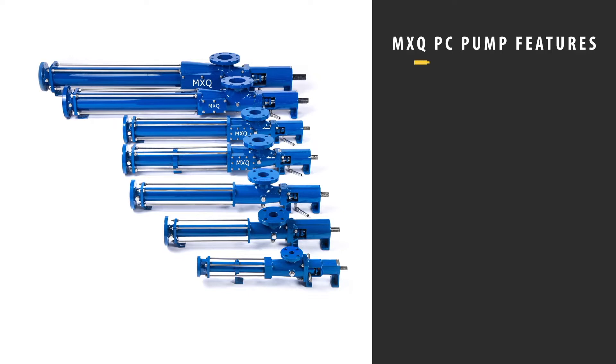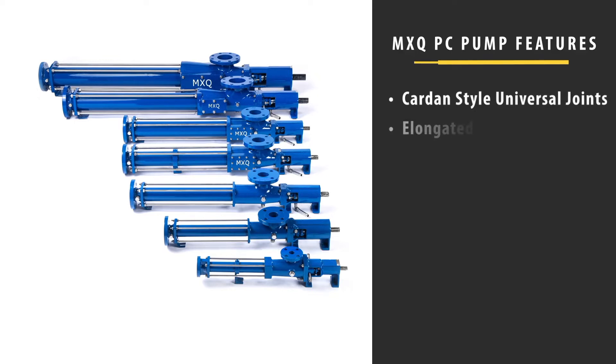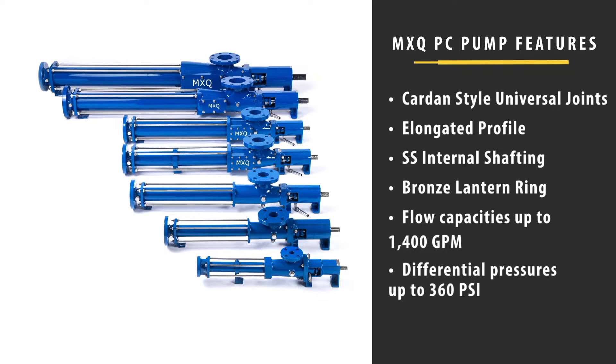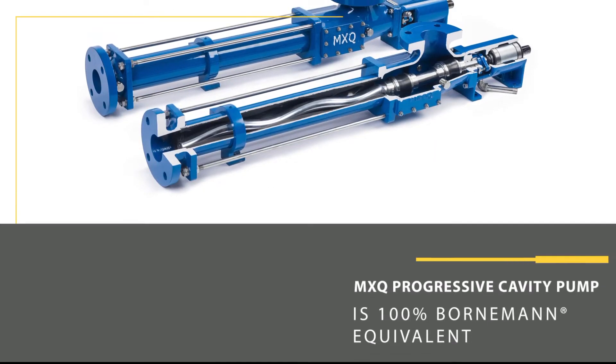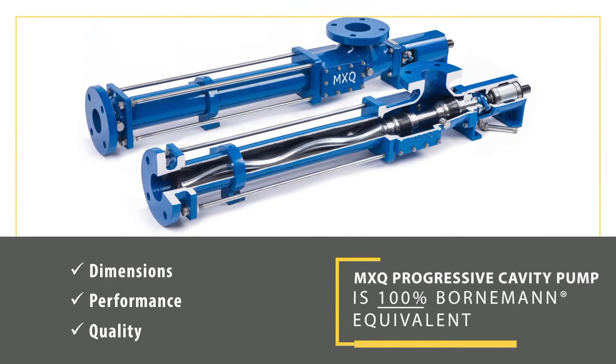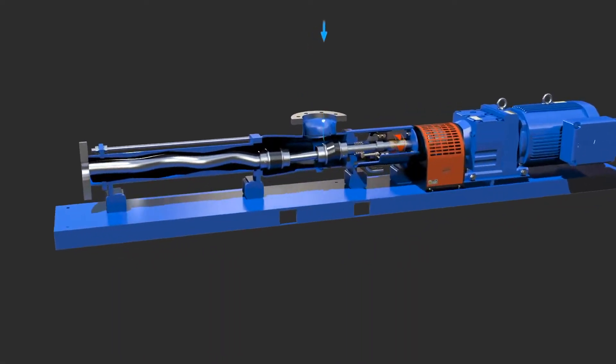The MXQ progressive cavity pump has various features that set it apart from the competition. Cardan Style universal joints provide a three-year warranty. The elongated profile requires a lower RPM, resulting in less wear and maintenance. Stainless steel internal shafting allows for corrosion resistance and longer wear. A bronze lantern ring allows for better lubrication in the stuffing box. Flow capacities up to 1,400 GPM and differential pressures up to 360 PSI.